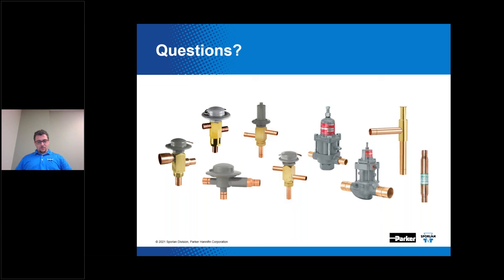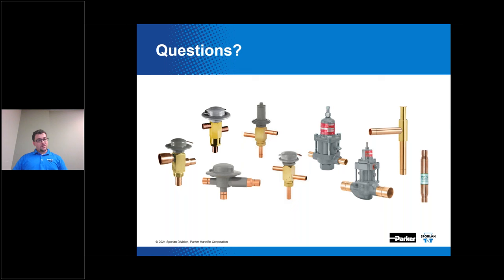Question: When would you want to flood the condenser during the summer? You really do not want to flood the condenser during the summer. Flooding of the condenser is really only designed to be done during low ambient conditions to keep that head pressure from falling too low. If the condenser was properly sized for the worst case — the dead of summer — you don't want to flood it during the summer because that condenser needs the ability to reject all that heat.